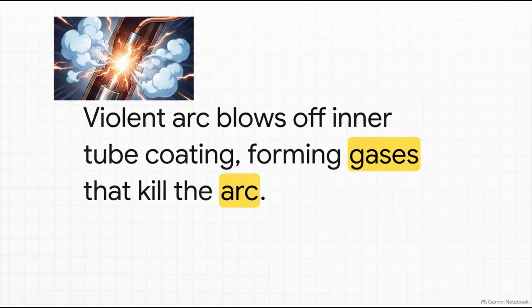These are super common for feeders and transformers simply because they're cost-effective. Developed for 11 kilovolt systems, these things boast a rupturing capacity of up to 250 MVA, which is just massive. So, they're made of a hollow open-ended tube constructed from synthetic resin-bonded paper. When this fuse blows, it generates a wildly violent electrical arc. But that arc is so intense, it actually blows off the inner coating of the tube itself. And when that coating vaporizes, the resulting gases form instantly to extinguish the arc. The destructive force literally creates the very gas it needs to save the whole system.